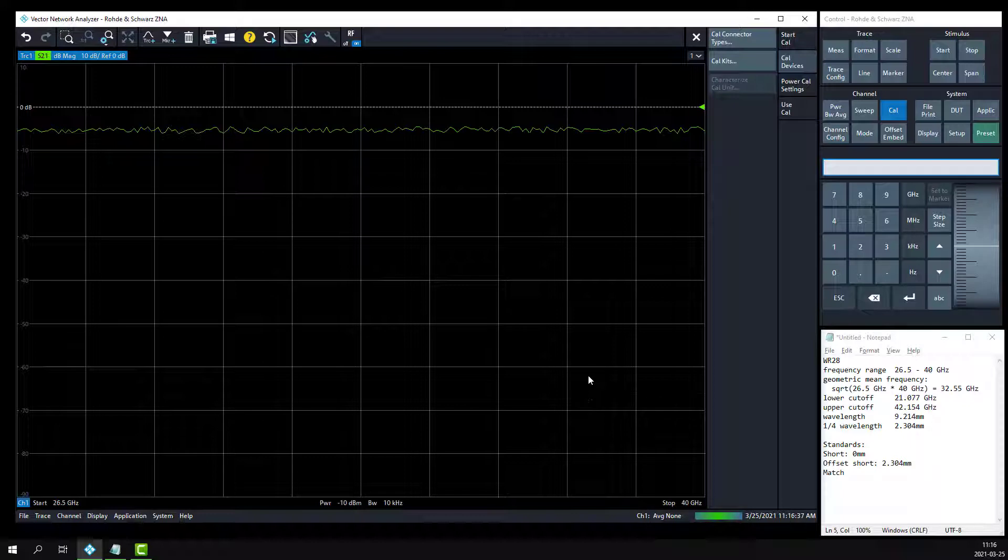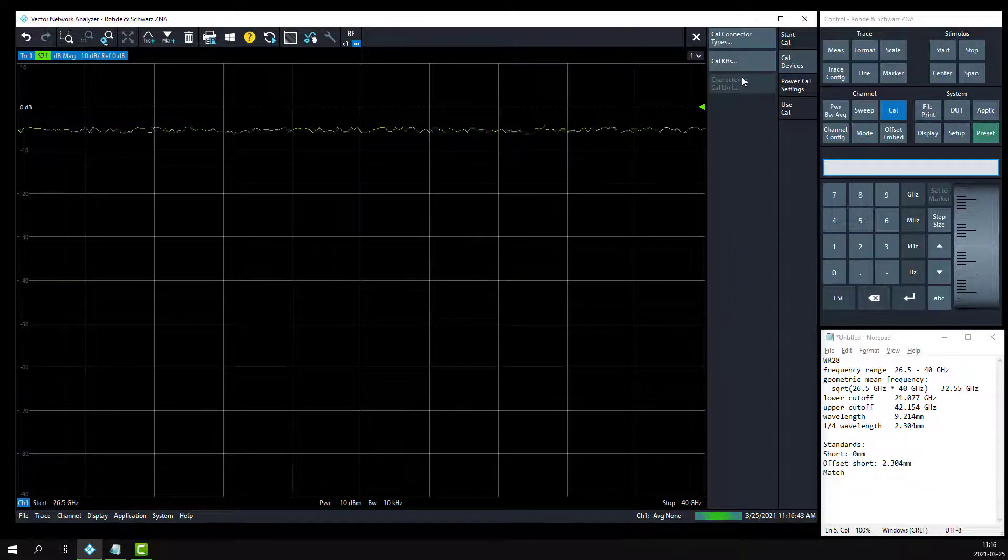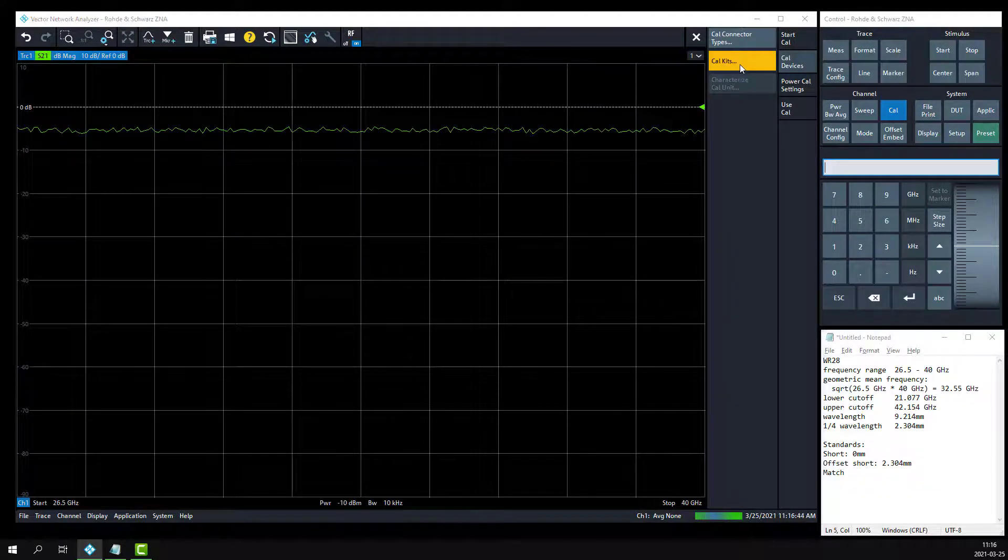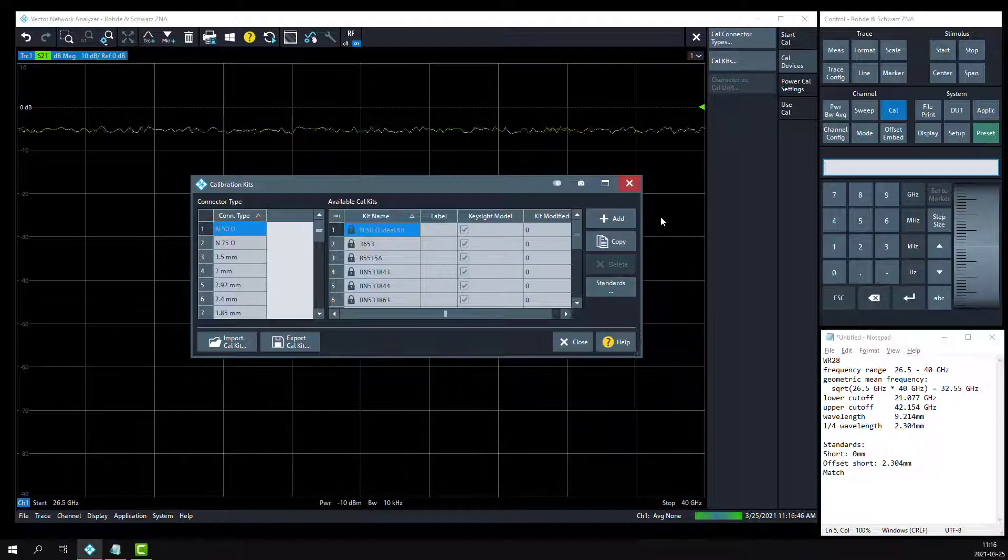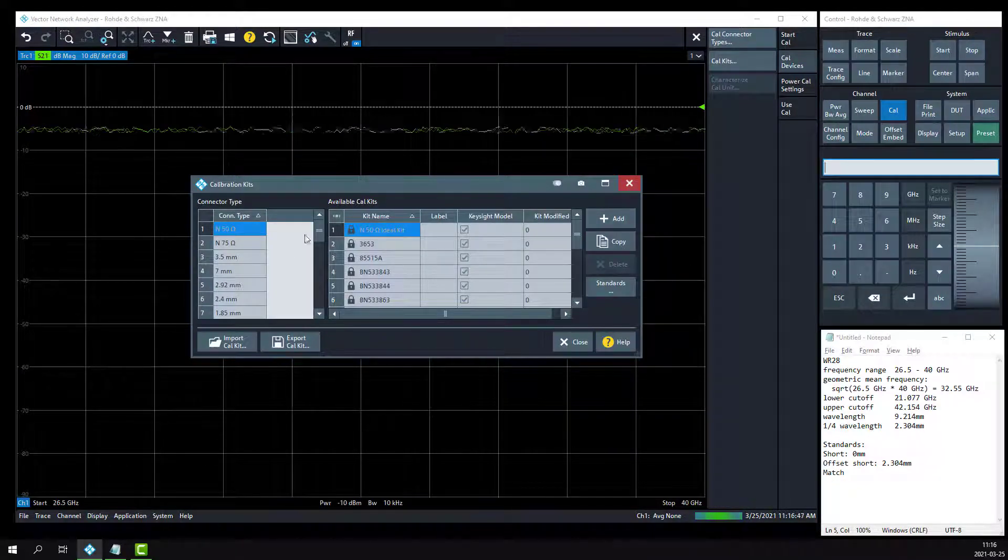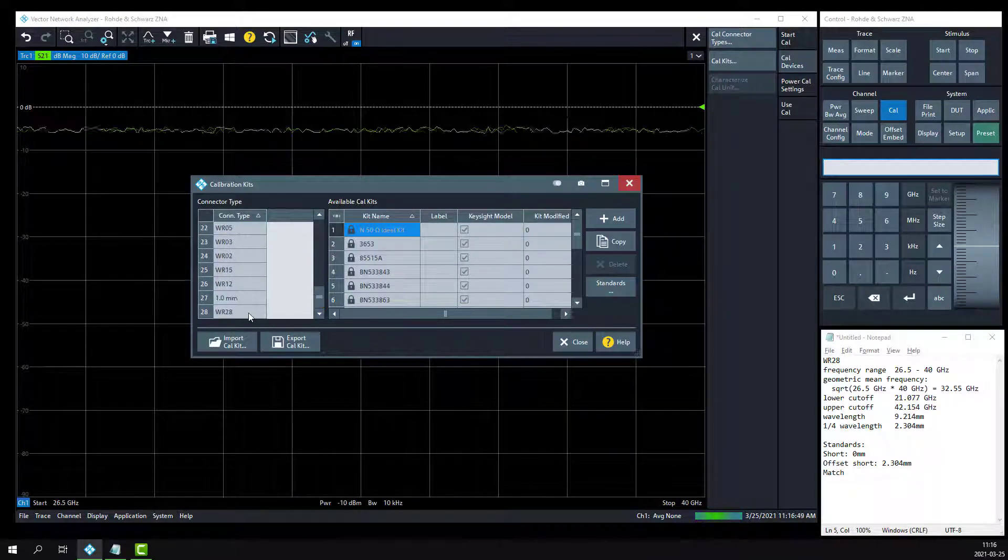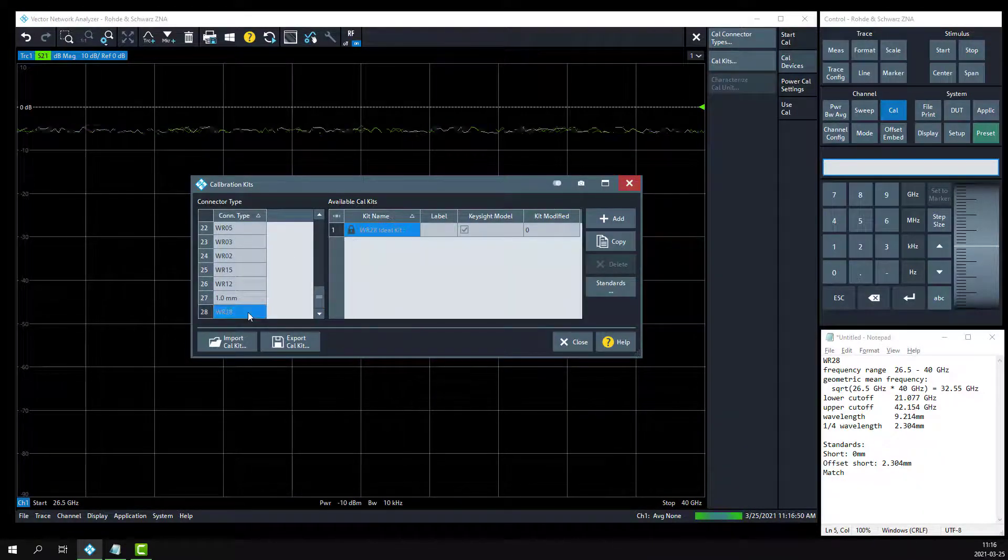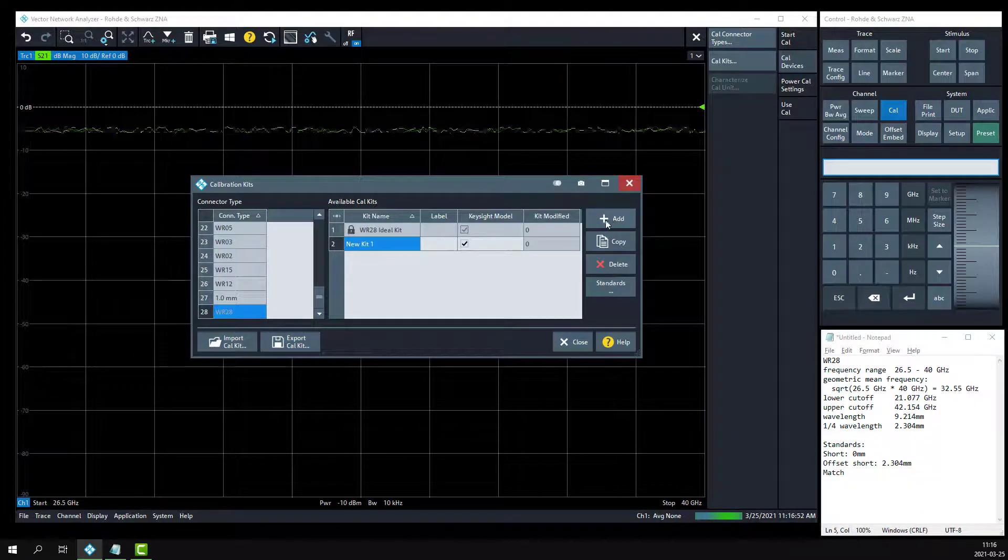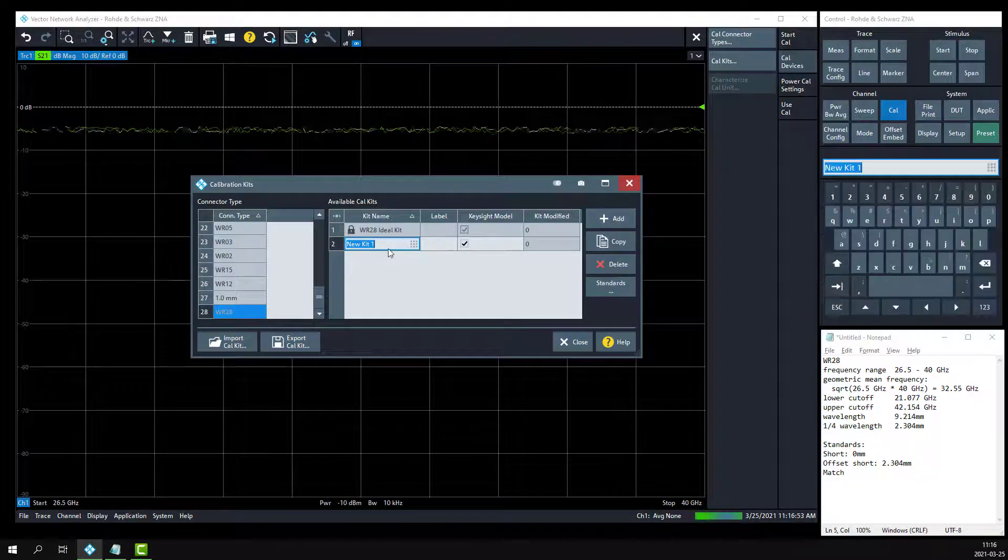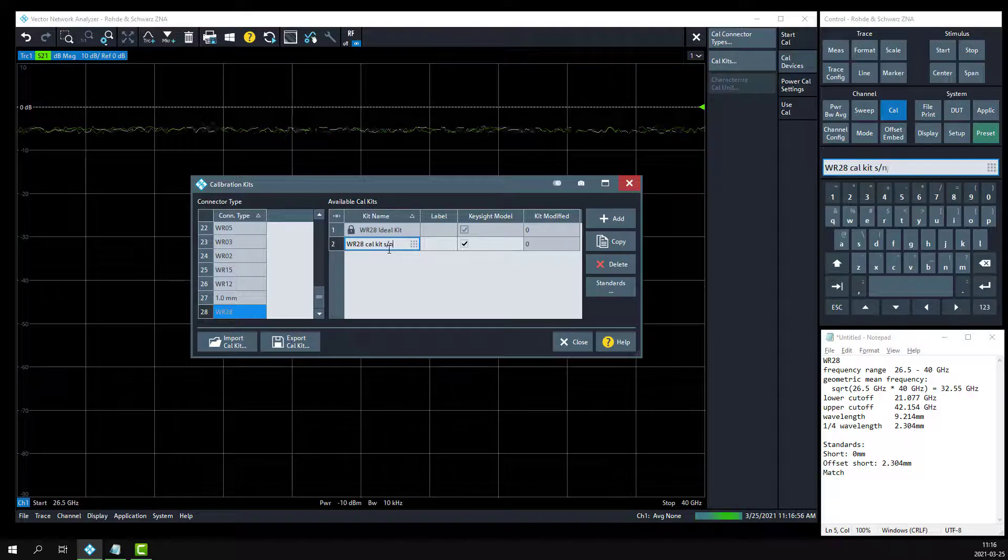The third step is to define my WR28 calibration kit, including the mechanical lengths. I'm going to click on the Cal kits button, scroll down to the WR28 connector type, and we're going to add a new WR28 calibration kit. Let's call that WR28 Cal kit, serial number 1.